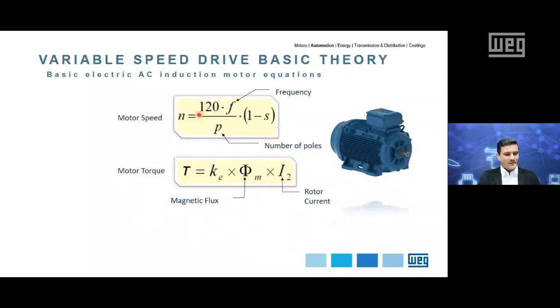Since we are talking about VSDs, which are used to control and protect electric motors, let's also review some basic AC induction motor equations first. Motor speed is defined by 120 multiplied by frequency divided by the number of poles, multiplied by 1 minus slip. Just keep in mind that the number of poles and the slip are motor characteristics. So in order to change the motor speed, it's required to vary the frequency parameter. And this is exactly what the VSD will do.